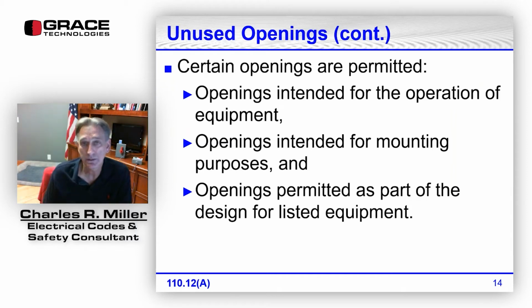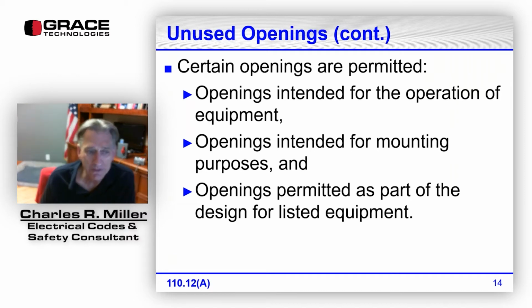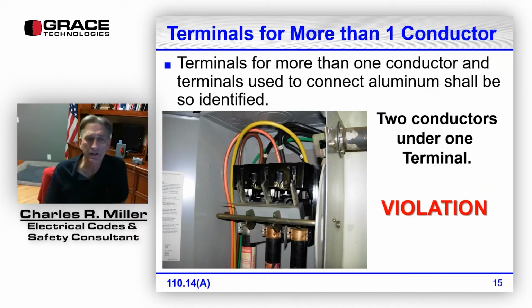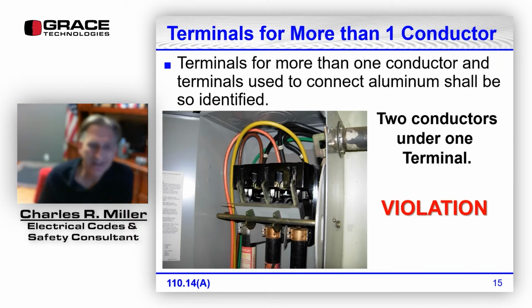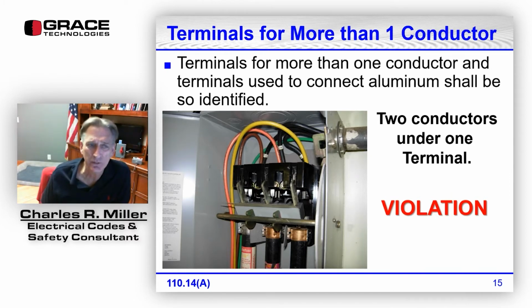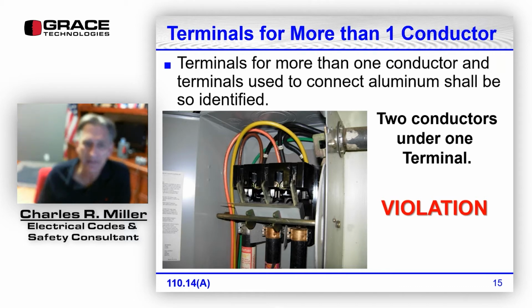All right, so you have holes in junction boxes and in panelboards that are intended for mounting purposes. Holes like that do not have to be closed. It really went without saying for years and years, but now it is specifically stated as such in the NEC. 110.14(A), terminals for more than one conductor and terminals used to connect aluminum wire shall be so identified.